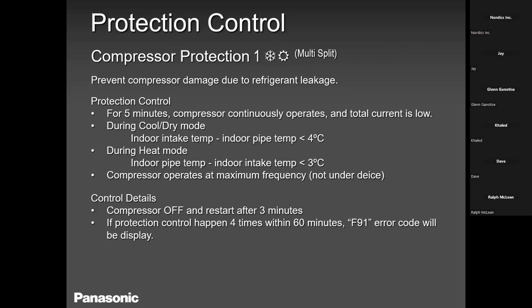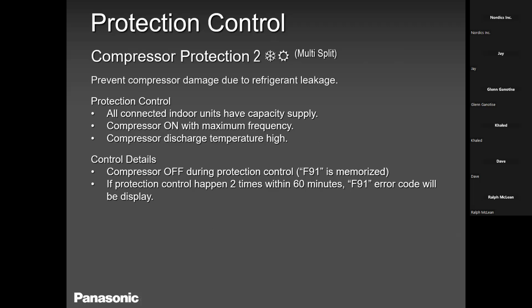F91, with multi-zones, it's most likely low on gas. I have a lot of experience with F91 error where the unit was low on gas, no leaks but low on gas. So how the gas disappeared, I don't know, but basically F91 is the number one error on multi-zones when the system is low on gas. Also, if the system has been running for a while and you don't think the problem is with the refrigerant, then it could be the indoor sensors. Okay, it could be the indoor sensors in cool mode that is giving trouble. So it all depends, guys. Okay, it all depends.